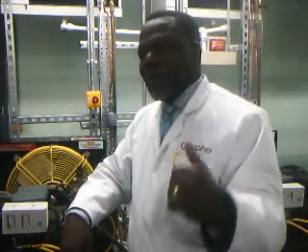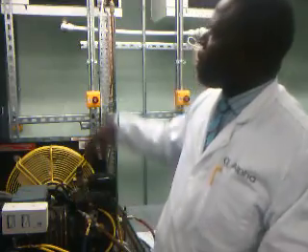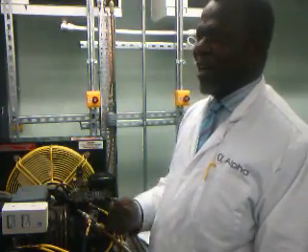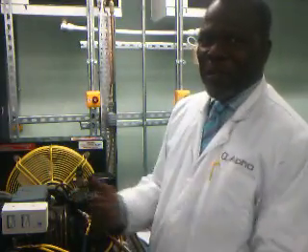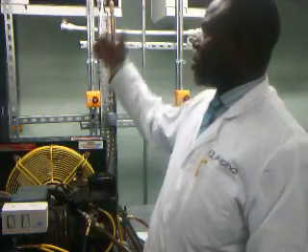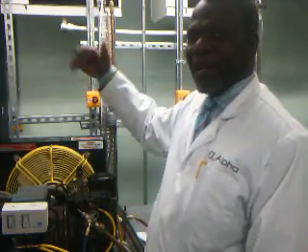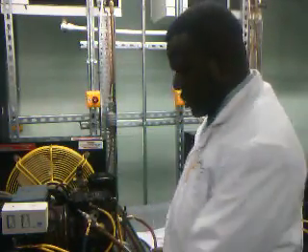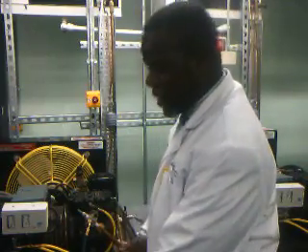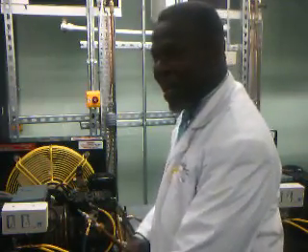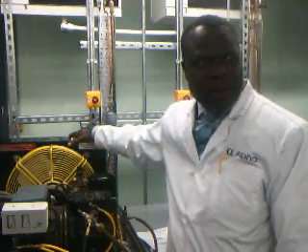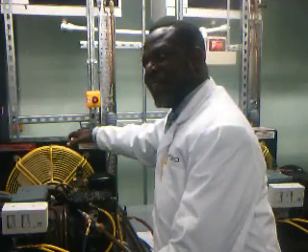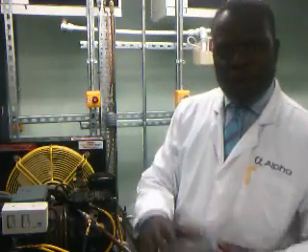Yes, you have to confirm, because when you install a unit and you are getting the right superheat, you know it's working. You've got the right amount of gas. You're taking the temperature in the evaporator. You are getting the right temperatures. You check your back pressures, and the back pressures are correct, your temperatures are okay, you haven't done subcooling, but you know straight away that it's good. But then you still have to confirm it.